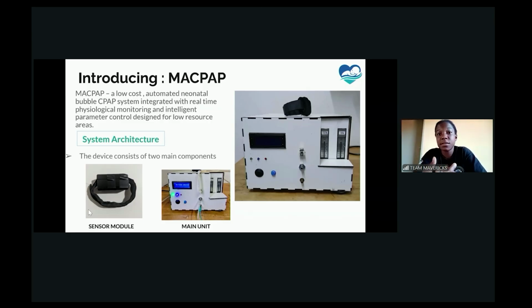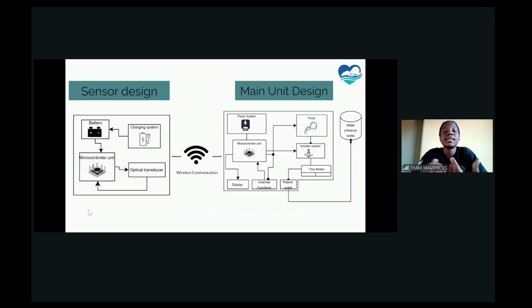The device is made of two components: the sensor module and the main unit. The sensor module is self-contained with its own power management, continuously sending real-time vitals wirelessly to the main unit. This allows the main unit, which houses the pump and actuator, to be positioned safely at the bedside. By separating the sensor and main unit, we've eliminated the need for bulky wires between the two.